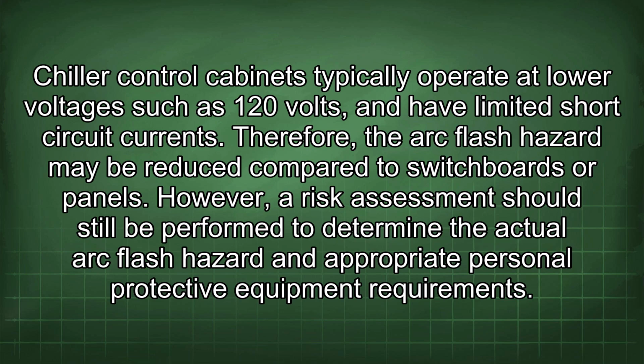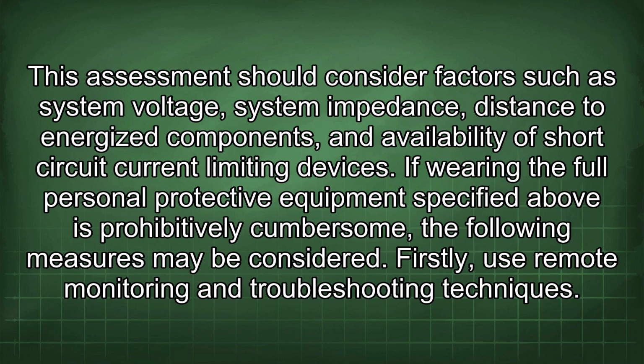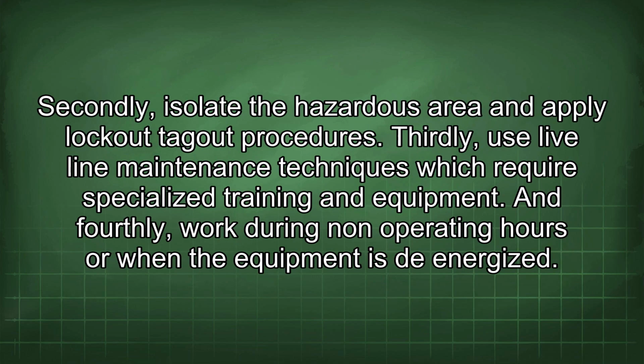However, a risk assessment should still be performed to determine the actual arc flash hazard and appropriate personal protective equipment requirements. This assessment should consider factors such as system voltage, system impedance, distance to energized components, and availability of short-circuit current limiting devices. If wearing the full personal protective equipment specified above is prohibitively cumbersome, the following measures may be considered. Firstly, use remote monitoring and troubleshooting techniques. Secondly, isolate the hazardous area and apply lockout-tagout procedures. Thirdly, use live line maintenance techniques which require specialized training and equipment. And fourthly, work during non-operating hours or when the equipment is de-energized.